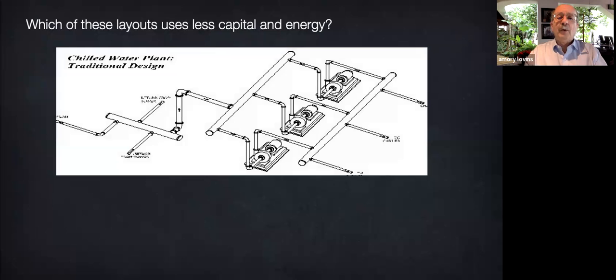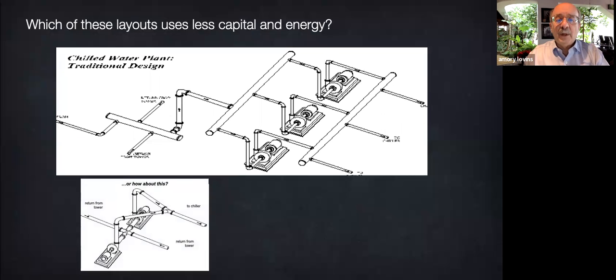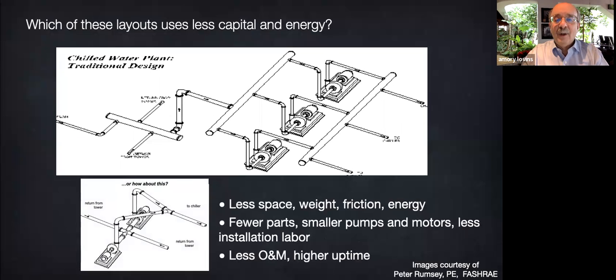Similarly, here's how most big buildings pipe cooling tower water back to the condenser. But if we lay it out instead the way Peter does, everything gets better. Less space, weight, noise, friction, energy, fewer parts, smaller pumps and motors, less installation labor, less maintenance, higher uptime. The only obstacle is force of habit. Bend minds, not pipes.